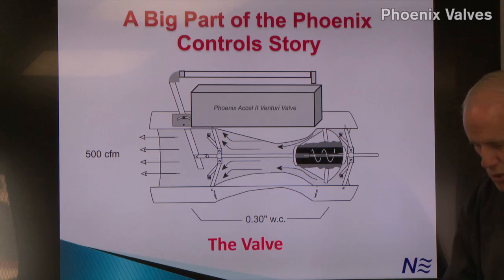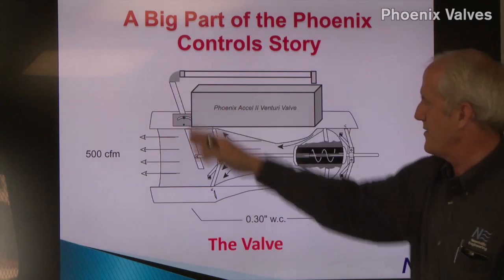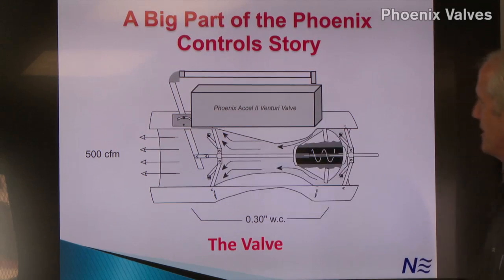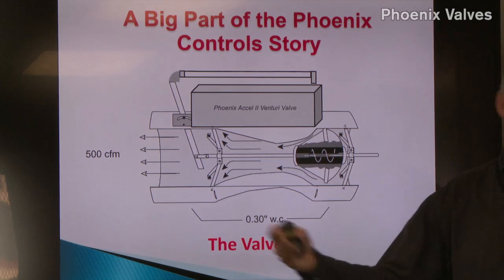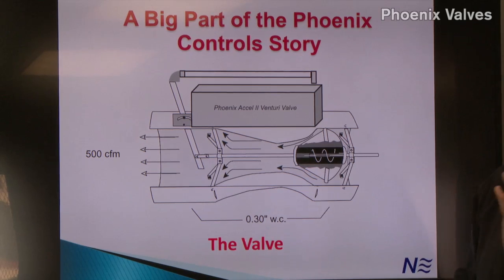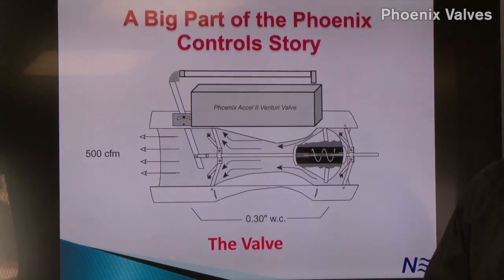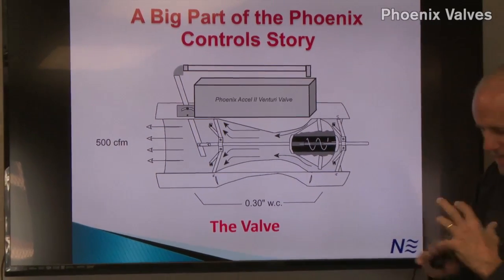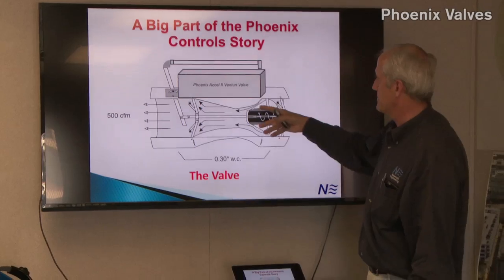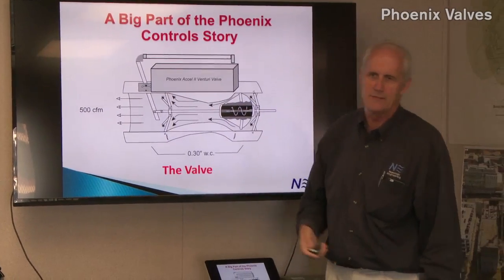So basically we're going to set this shaft to a position, and that's the 500 CFM position, and we're good to go. And you say, wait a minute, but what if the pressure changes? Those remote devices, you set the damper, and then the pressure changes, and you have to adjust your damper to try to keep it at 500. All that adjustment is happening in here with this cone and spring assembly.